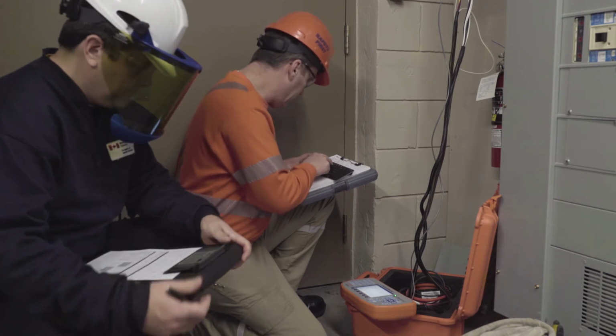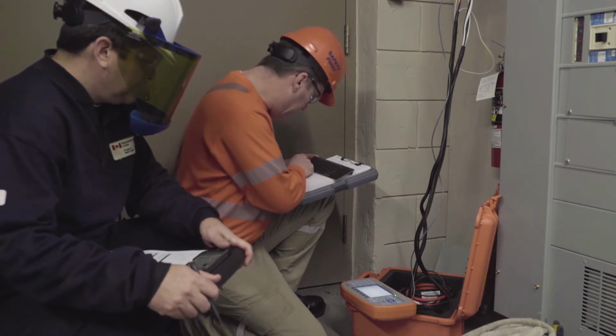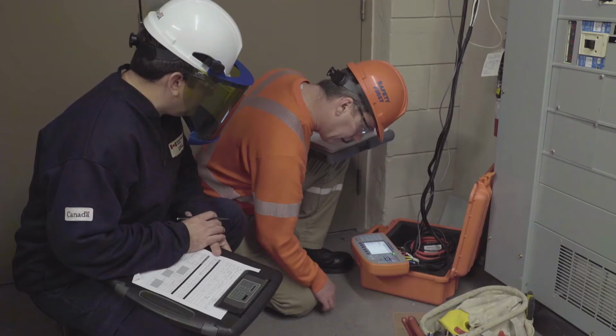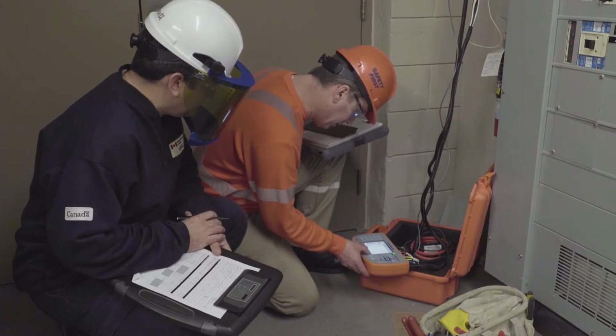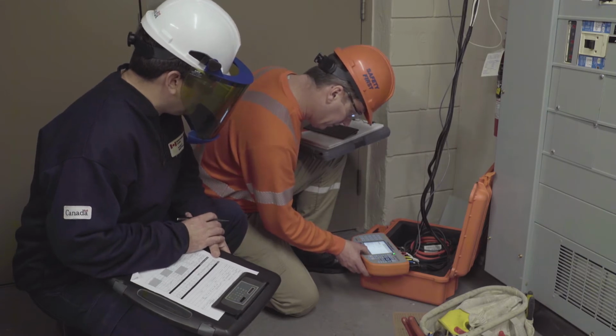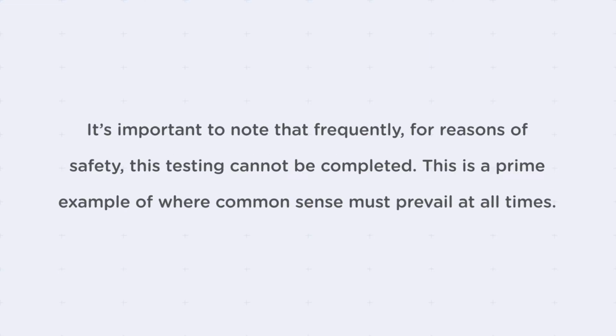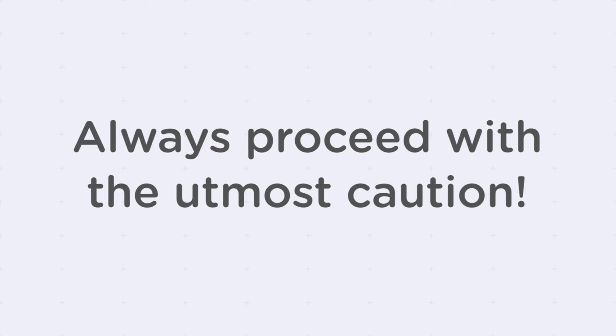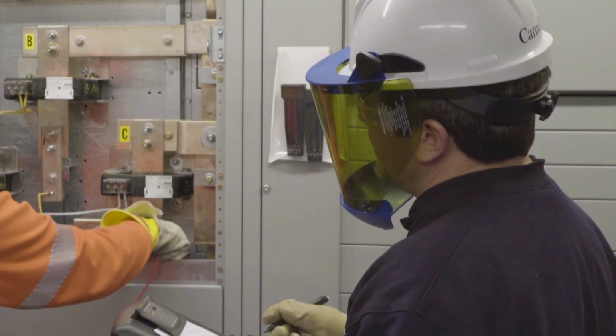In some instances, the secondary current is not available at the test block, in which case a second ammeter will be required to measure the secondary current at a safe location between the CT and the meter. It's important to note that frequently, for reasons of safety, this testing cannot be completed. This is a prime example of where common sense must prevail at all times. The message here is to proceed with the utmost caution. If you are in any doubt as to the safety of making these connections, then don't do it.